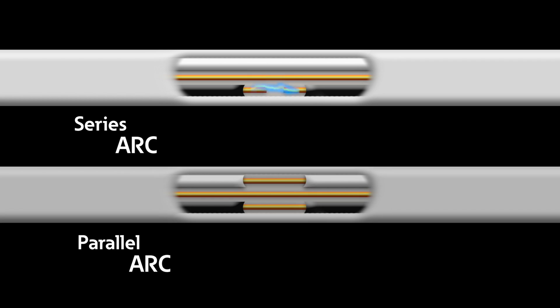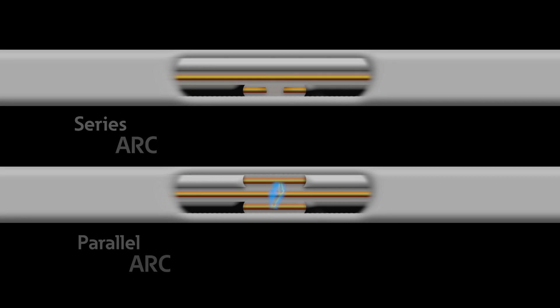Arc faults are often referred to as series or parallel arcs. A series arc occurs in one conductor and is a low level of current, which is in series with and limited by the load — it is often the result of a bent or broken wire. A parallel arc occurs between two parallel conductors and is a higher level of current because it is in parallel with and therefore not limited by the load. It can occur when nails or staples are driven through wires.